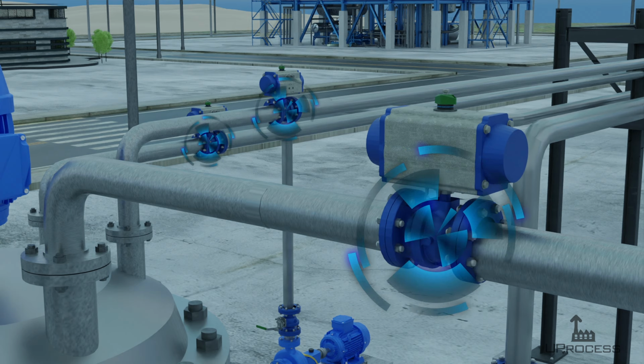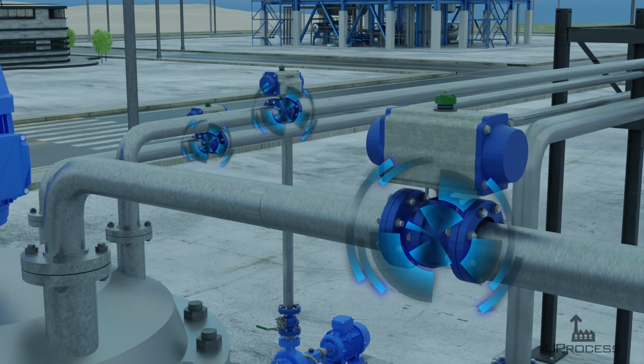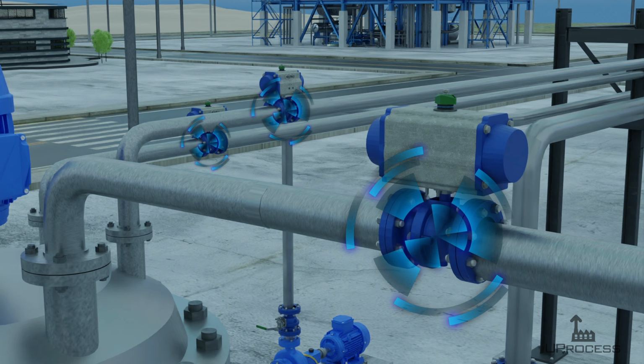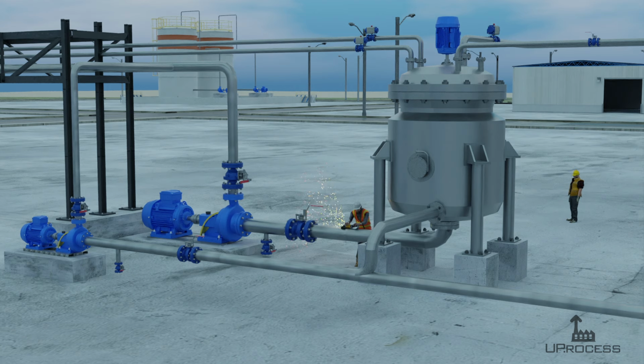As the valves mistakenly used as blocking were located at a significant height, a local inspection was not carried out to test the effectiveness of the isolation. After the accident, demonstration cuts were made in the workshop. It was found that as the abrasive wheel broke through the pipe wall, a small flame occurred, and the pipe itself glowed dull red.